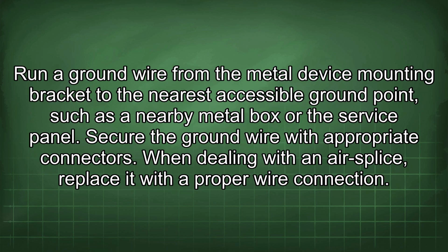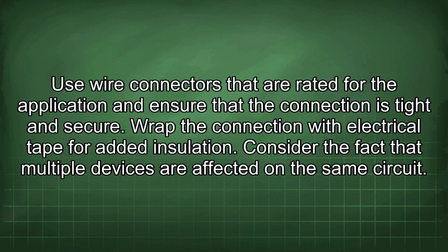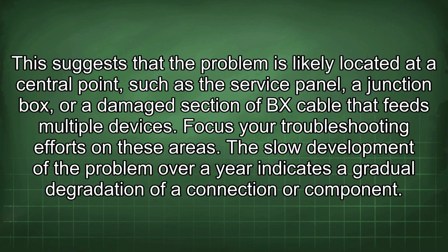Run a ground wire from the metal device mounting bracket to the nearest accessible ground point, such as a nearby metal box or the service panel. Secure the ground wire with appropriate connectors. When dealing with an air splice, replace it with a proper wire connection. Use wire connectors that are rated for the application and ensure that the connection is tight and secure. Wrap the connection with electrical tape for added insulation. Consider the fact that multiple devices are affected on the same circuit. This suggests that the problem is likely located at a central point, such as the service panel, a junction box, or a damaged section of BX cable that feeds multiple devices.